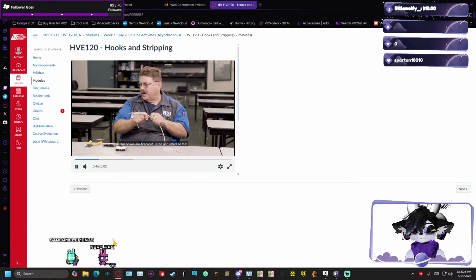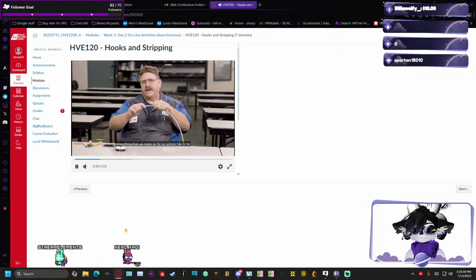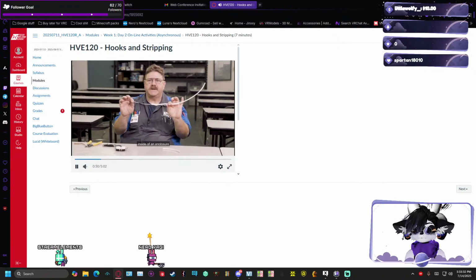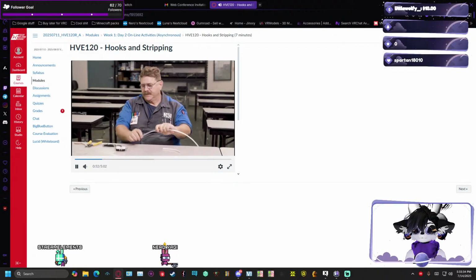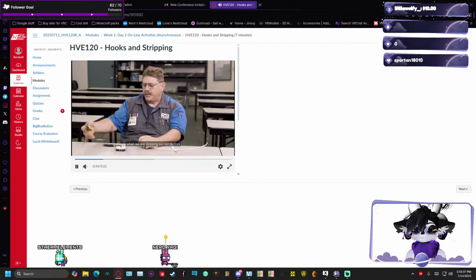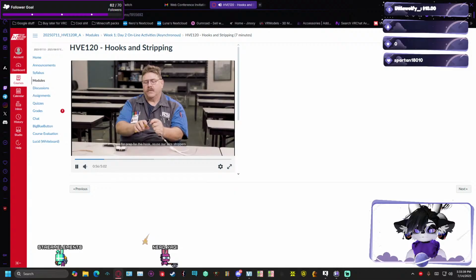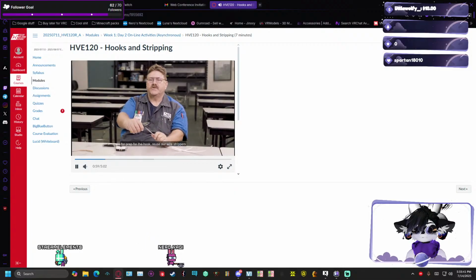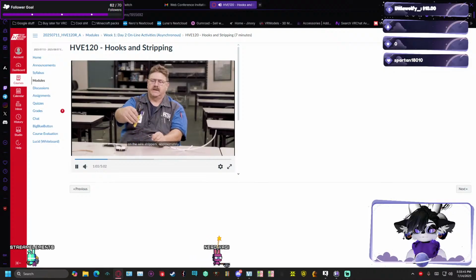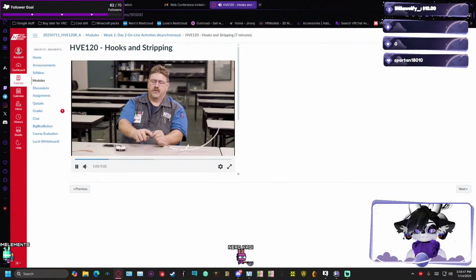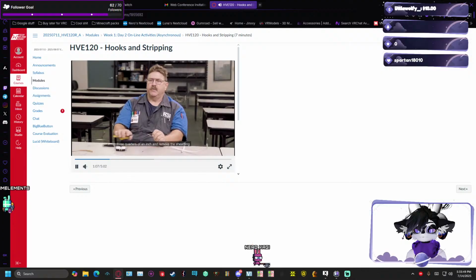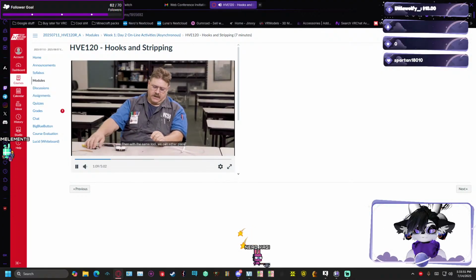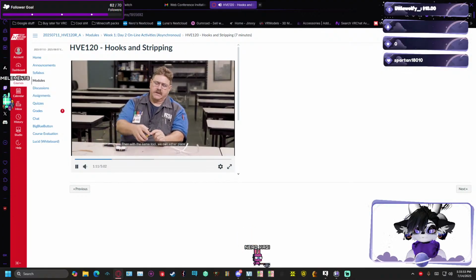Our boxes are fire listed and rated so that everything that we make as far as splices has to be inside of an enclosure. When we are stripping our conductors to prep for the hook, we're going to use our wire strippers, and we're going to go into the 14 gauge size on the wire strippers, approximately 3/4 of an inch, and remove the sheathing. And then with the same tool, we can either place it in the side and use the hole in the side of the tool to make a hook.